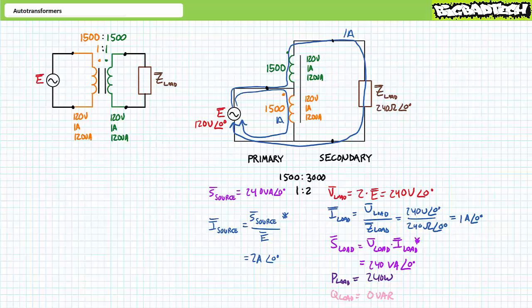Consider the amount of power capable of being transferred by the auto transformer. When configured as a traditional transformer, 120 volt ampere input resulted in 120 volt ampere output from an eight pound transformer. Configured as an auto transformer, the same eight pound transformer uses both windings — each with a 120 volt and one amp rating — and transfers a total of 240 volt amperes. Step-up auto transformers can transfer more power in a smaller, lighter, less expensive package; however, the single winding defeats the isolation feature. A doubling of power rating is the maximum one might expect to achieve; other turns ratios result in more power transfer, but not quite double.